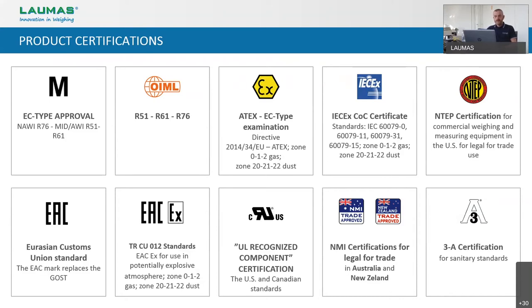As we can see in this slide, our transmitters are OIML approved for legal-for-trade applications according to NAWI — which is OIML R76 for non-automatic weighing instruments — and according to AWI for automatic weighing instruments, for which we have evaluation certificates according to R61 and R51. We have the NTEP approval for the US market and the NMI approval for Australia and New Zealand. We also have certifications for explosion-proof areas according to international regulations like ATEX or IECEx, and the TRCU-012, which is specific for the Russian market.